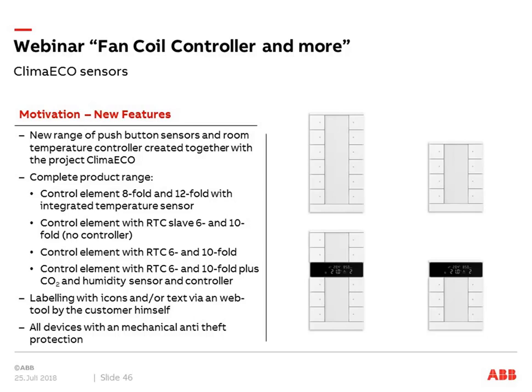Then we have control elements with RTC Slave functionality — 6 and 10-fold components with a display and integrated temperature sensor, but no controller inside, since we already have it in the fan coil controller. Using the RTC Slave together with FCCS gives full functionality, and the customer sees no difference compared to a classical room temperature controller. If desired, a complete room temperature controller with the same look and feel — display with 10 and 6 push buttons — is also available.